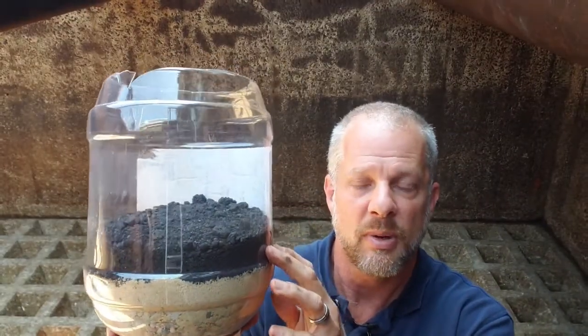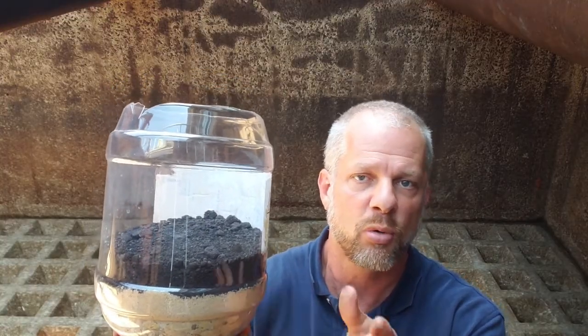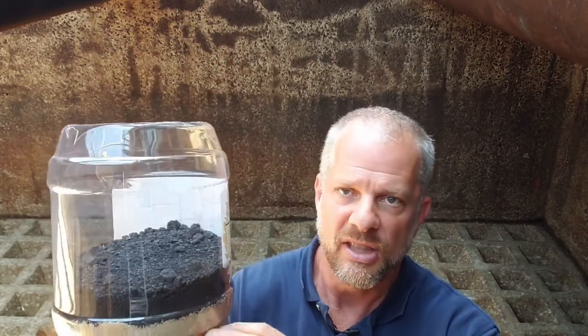So the top layer is about 18 inches of anthracite, which is a black crystalline material that does a great job of capturing anything that made it past the sedimentation and ozonation process. After that, there's about a foot of sand, and then the last layer is a foot of different size stone. Once it gets through these different layers, we're at the bottom, and this waffle-shaped structure here behind me is called a wheeler bottom. So the water is actually draining from the top of this chamber all the way through the bottom. So once that has happened, the water then goes to the disinfection process.